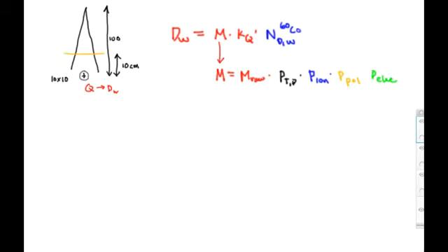So here we have all the formula together, and it's meant to be relatively straightforward. You find this raw meter reading, correct by all those factors we just talked about. You multiply by the KQ factor, you multiply by NDW that you get from the calibration lab, and that's your dose to water. Now this is one thing I'd like to mention. This is all measured at 10 centimeters depth in water, right?